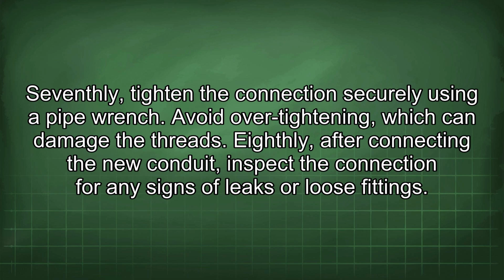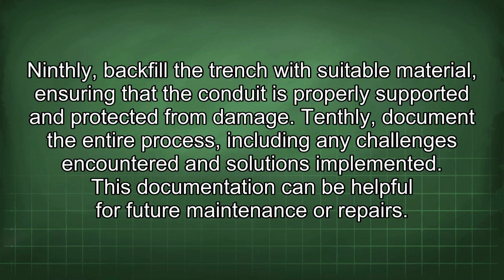Seventhly, tighten the connection securely using a pipe wrench. Avoid over-tightening, which can damage the threads. Eighthly, after connecting the new conduit, inspect the connection for any signs of leaks or loose fittings. Ninthly, backfill the trench with suitable material, ensuring that the conduit is properly supported and protected from damage. Tenthly, document the entire process, including any challenges encountered and solutions implemented. This documentation can be helpful for future maintenance or repairs.